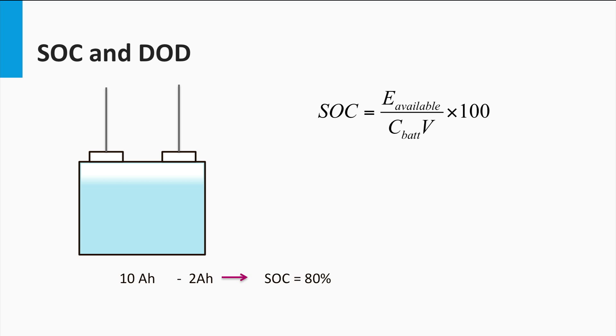Then we also have the depth of discharge or DOD. Depth of discharge is defined as the percentage of the battery capacity that has been discharged. Thus a 10 Ah battery that has been drained by 2 Ah has a depth of discharge of 20%. Thus the depth of discharge and the state of charge can be seen as complementary to each other.